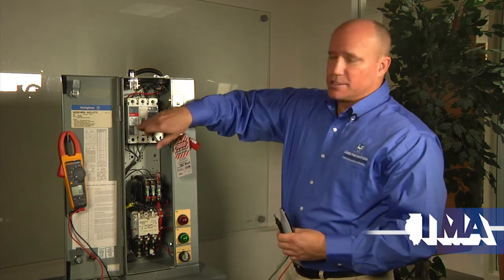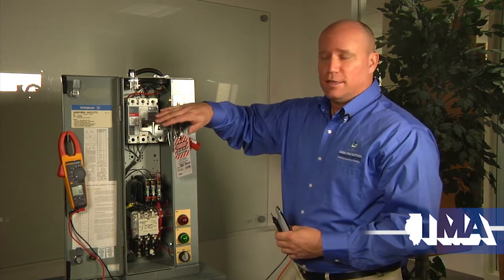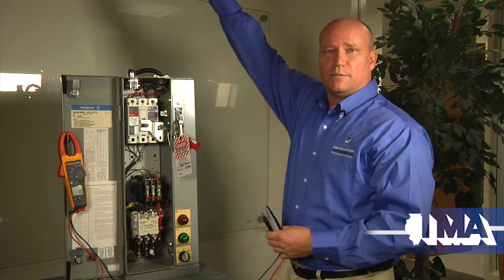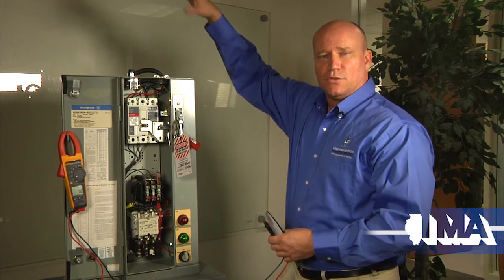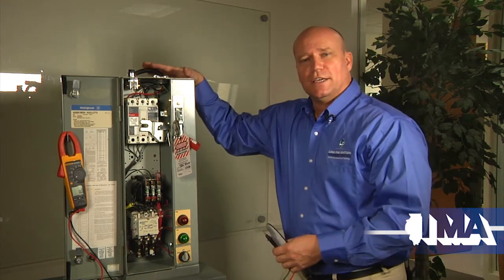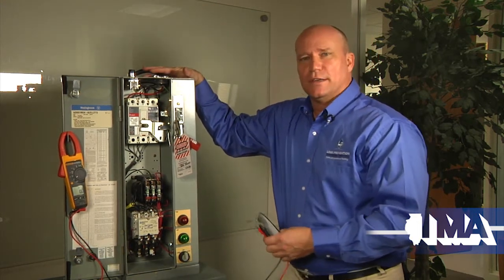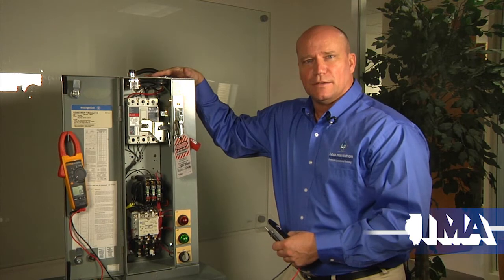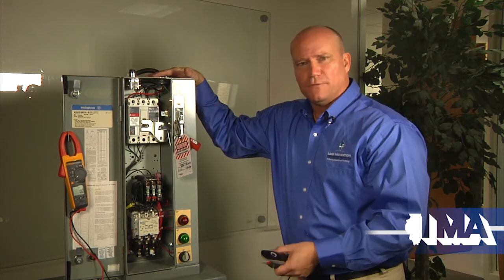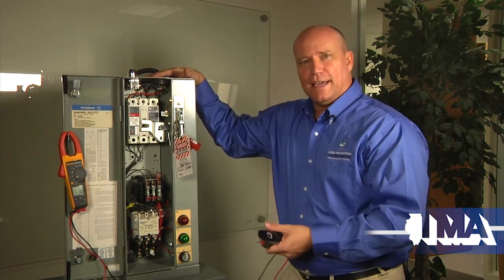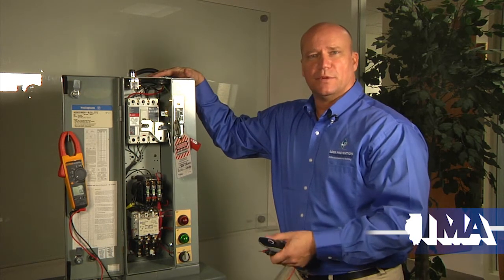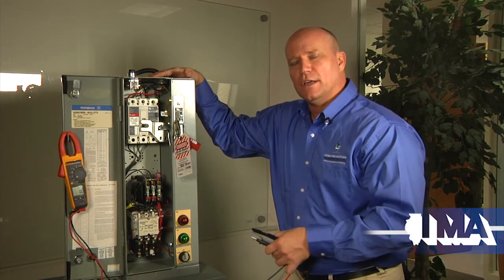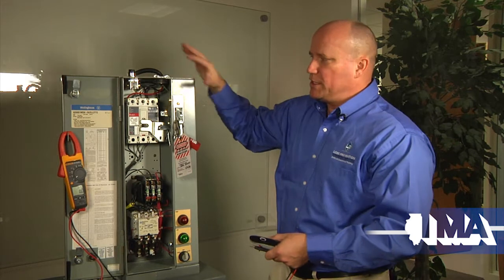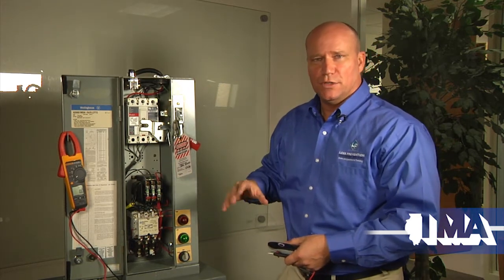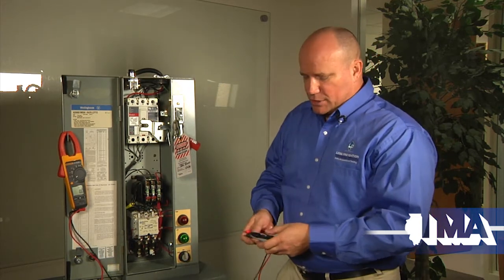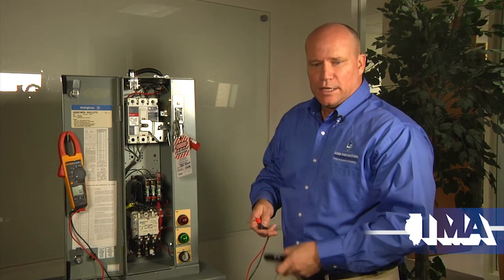If it was because this breaker failed, we can still conduct this maintenance by isolating upstream, so we have to shift our isolation points. If we found voltage because we got the wrong breaker, it was your mistake. You go back, you've identified, hey, I should have been on circuit breaker number 3, but I got circuit breaker number 5. Well, that can be adjusted as well, but you want to place your work area in a safe condition before you do that.